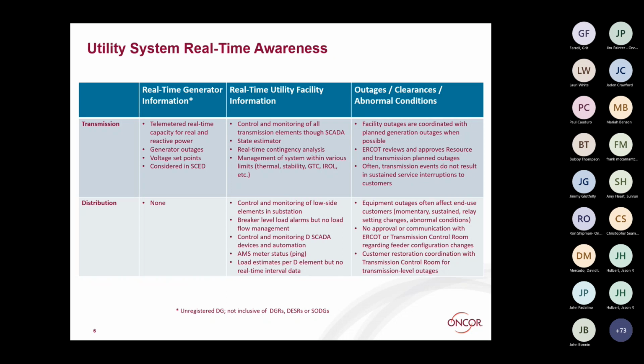And I may also want to make a point on the AMS system, the automated metering system. It provides us new insight and visibility on the very far edge of the customer list, on that meter. But it is not like SCADA. It is not a real-time control or monitoring system. While we are getting interval data every 15 minutes in terms of consumption and maybe some operational parameters like average voltage, all that data is collected at a meter, but not downloaded into the back office database at the utility until hours after it's measured. So, depending on the setup for each utility, in our case, we may have a download once a day, but not every 15 minutes.